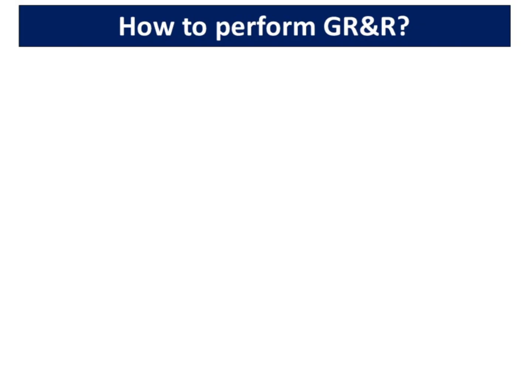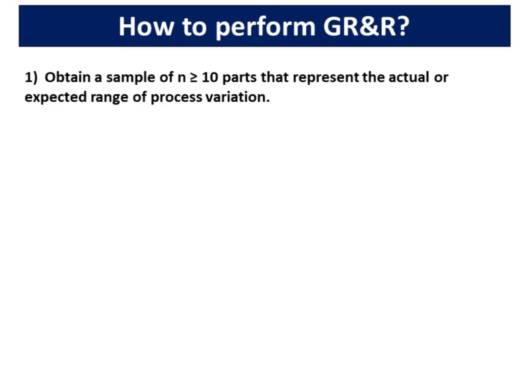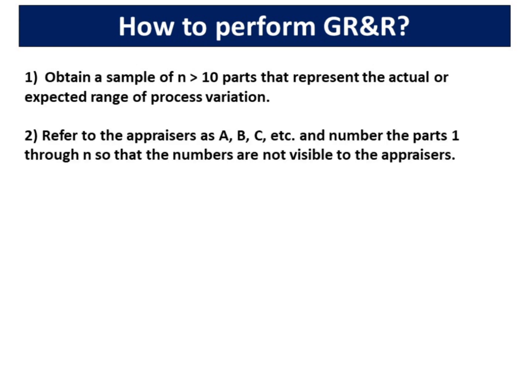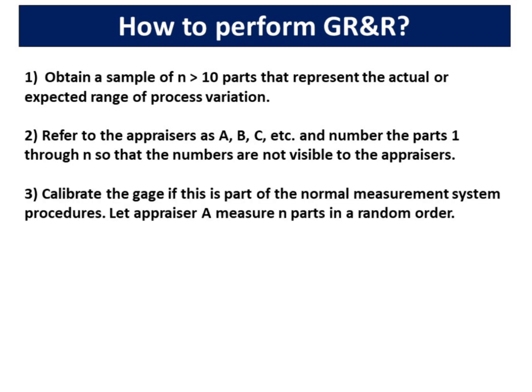How to perform GR and R. Step 1: Obtain a sample of N greater than or equal to 10 parts that represent the actual or expected range of process variation. Step 2: Refer to the appraisers as A, B, C, etc., and number the parts 1 through N so that the numbers are not visible to the appraisers.